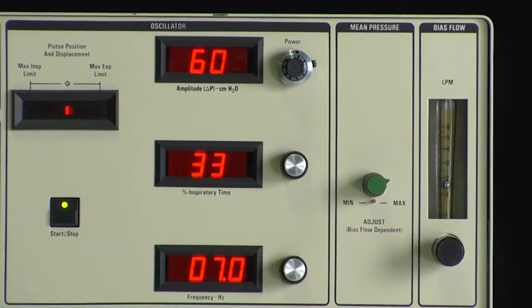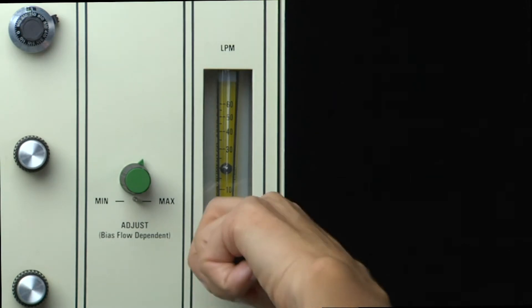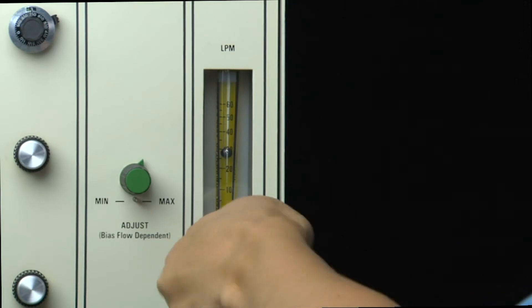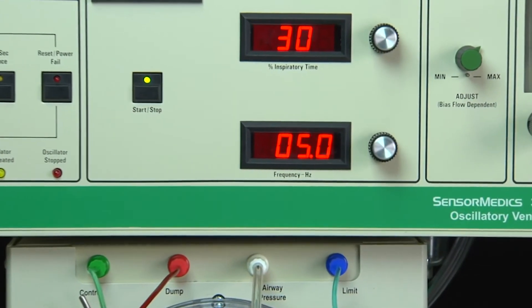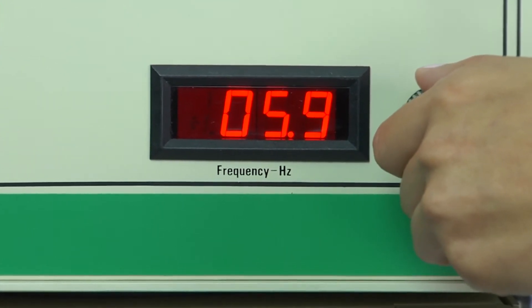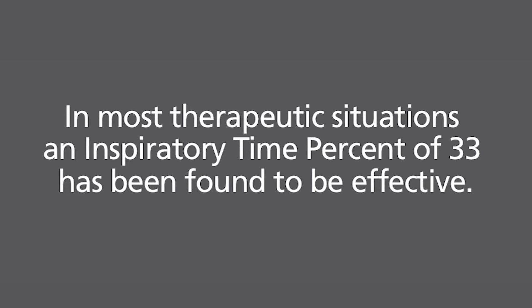The controls for bias flow, frequency, and inspiratory time percent are rarely changed during the course of treatment. Typically, the bias flow is maintained within the range of 25 to 40 liters per minute. In practice, as patient size increases, starting frequency is decreased. For adult populations, frequency is typically initiated at 5 to 6 hertz. Although some cases may benefit from an inspiratory time percent of 50, in most therapeutic situations an inspiratory time percent of 33 has been found to be effective.